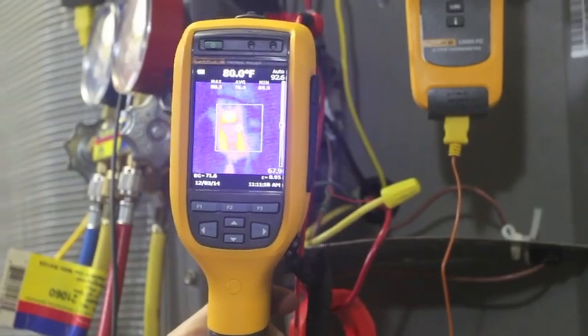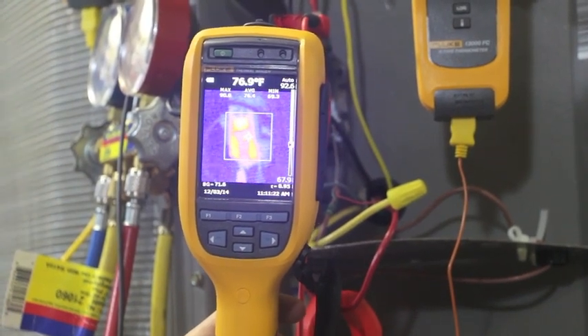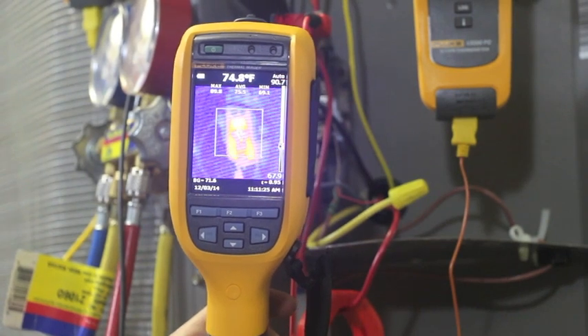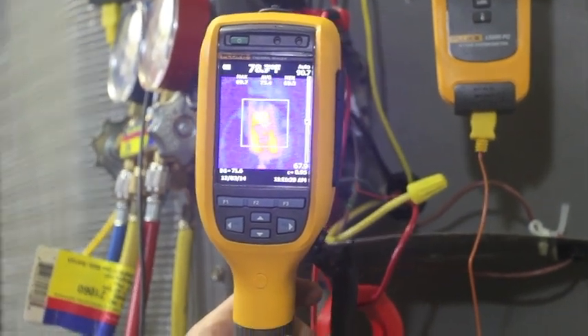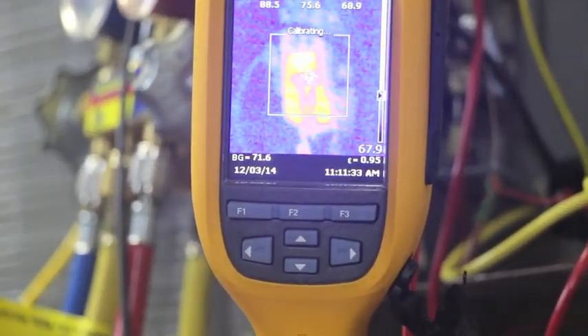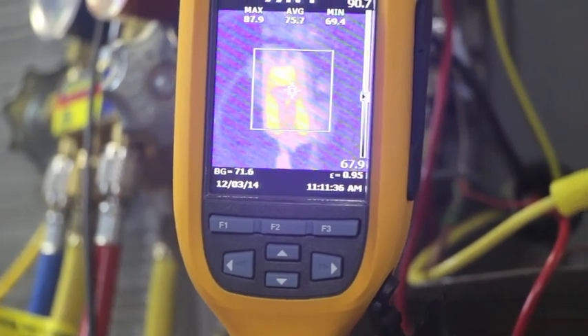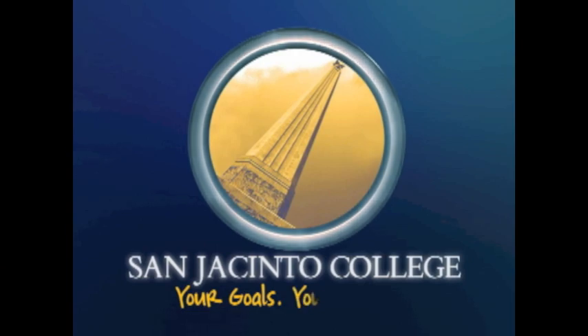Starting up the compressor, we saw low voltage, so we used the thermal imager and found a loose connection. As you can see, the connection is glowing. We're going to stop and correct this problem and then proceed.